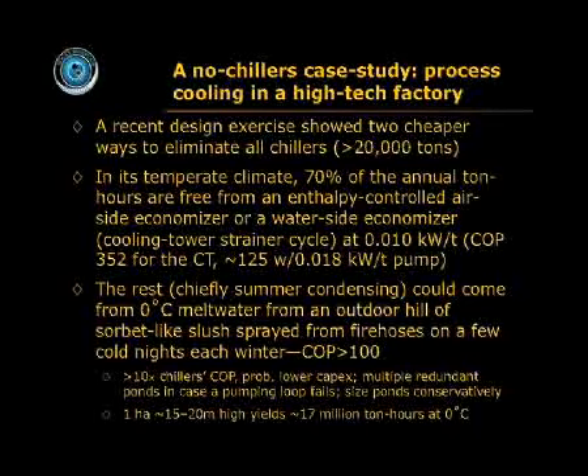Well, the other 30% of the ton hours, in this case mainly for summer condensing, we were able to get by creating what we called Mount Sherbet. We would go out at night with a fire hose about 5 cold nights a year. It did get cold in this place, below, say, -2°C, and we'd simply spray a mountain of slush in some unused land they had out back, and that was COP probably hundreds. So it was over 10 times as efficient as a chiller, and it would cost a lot less. And a hectare, 15 or 20 meters high of slush would yield about 17 million ton hours of zero-C meltwater through the rest of the year.